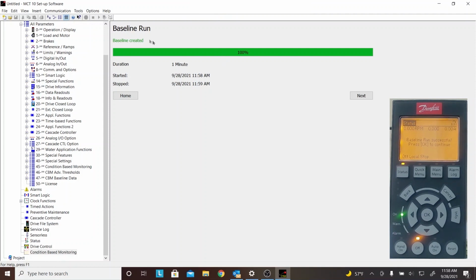So it's really unique. So we've created the baseline, and you see the green baseline created, and we're at 100% ISO colors here. And even the keypad says, hey, we're successful. Press the OK button in the center to let us know. So good, we've acknowledged everything. So now we're back in the off position. The motor has stopped running. So we ran from 100 to 1700 RPM on the motor. We've gathered all the data for vibration, motor, stator, and load, and we're ready to move forward.